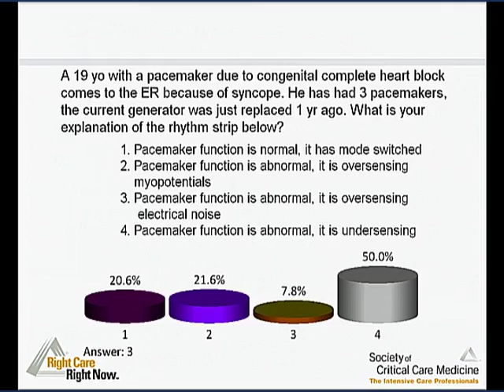Most think it's undersensing. Undersensing causes pacing where it shouldn't occur. And that's not the real problem here. The real problem is that it's oversensing electrical noise. And you see, here is a native QRS here, and we infer what the pacemaker interval, or the inverse of that, its rate, is set at by the interval between any two consecutive spikes here. And then we work back and say, okay, that's where it's sensing this previous one. So everything's okay here so far. Everything's still pretty okay.